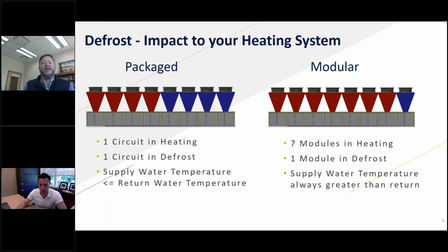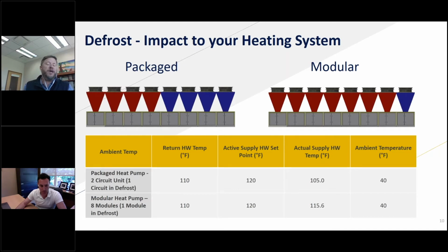And so when we start thinking about how we design our system and how many units we have and what type of redundancy we want to build in, we'll talk about that later, but how many units we have, what the defrost part of the conversation plays into, what does the mix of that system look like, so that we don't see, because I'm going to show you in our next slide, what the actual impact is to your heating system when we're in defrost. Now this isn't something that happens for an hour, but it can happen for 5 or 10 minutes potentially. What you see is I'm comparing the 2 setups. We've got a single packaged unit with 2 refrigerant circuits in the top row, and then the bottom row is the setup where we have 8 individual units, whether they be modular or packaged.